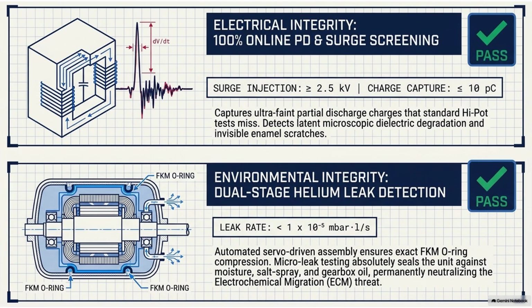But electrically, a scratch is a disaster. Completely. A scratch reduces the thickness of the dielectric. In electromagnetics, electric fields concentrate at sharp edges and thin points. Oh, right. That microscopic scratch becomes a focal point for intense electrical stress. The partial discharge will initiate exactly at that scratch, basically boring into the wire like a laser. The plus or minus 1 Newton tension control guarantees absolute physical perfection, 0 microscratches during winding.